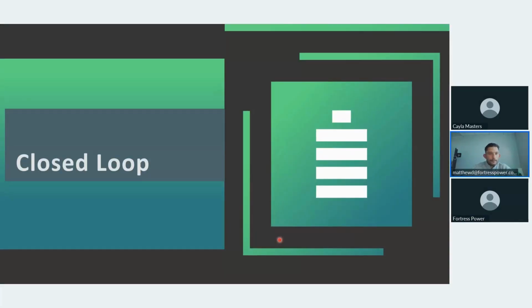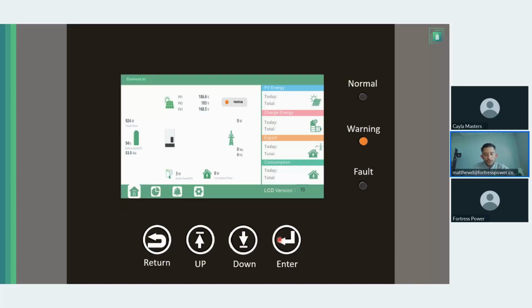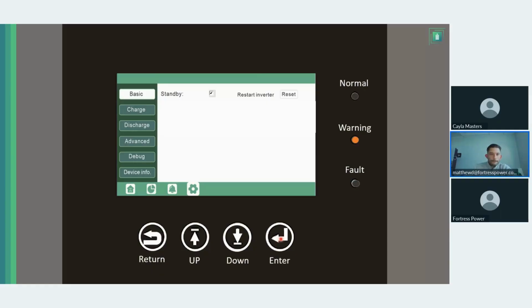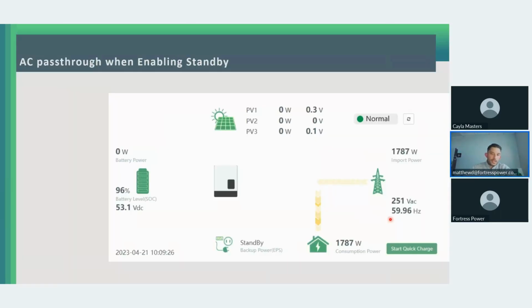Okay. Closed loop. How to achieve closed loop, right? We energize the battery. We energize the inverter. Now we're going to do closed loop with the inverter. Set the inverter in standby. Right, this is how it's going to look like in standby if you're grid-tied, right? It's going to do AC pass-through, assuming you have whole home backup.